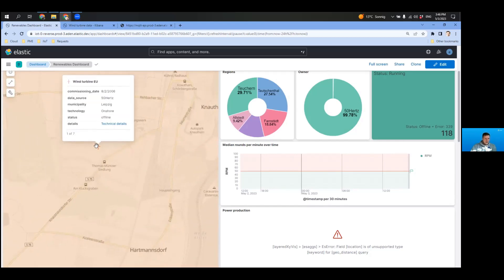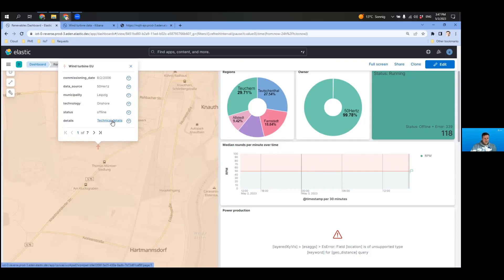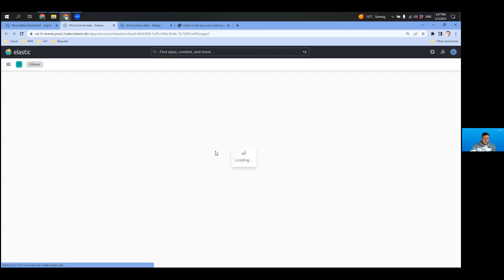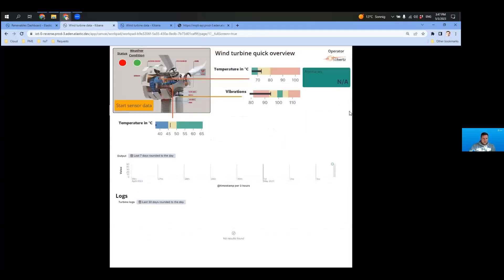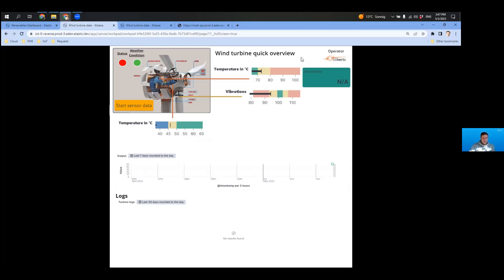We click on the specific wind turbine that has an issue, then click on the technical details, and we get all the information we need to learn more about what is happening at this specific machine. We don't have any anomalies here for this machine — that's how we got this little issue. We can also see temperature on the specific generator part, the vibrations, and what the min, max, average, and current values are. We can even get logs collected from this specific machine. We now see there is no output and no log, so it looks like the turbine is just offline. Somebody needs to go to the wind turbine and activate it again — this cannot be done from a remote connection because there is no remote connection anymore, though we can still get the sensor data.